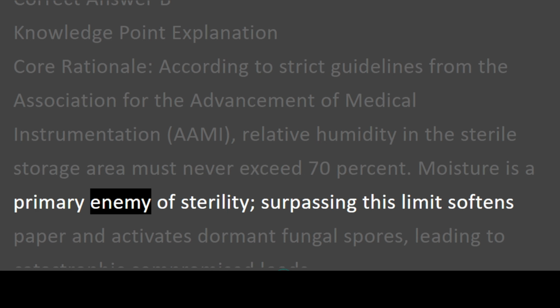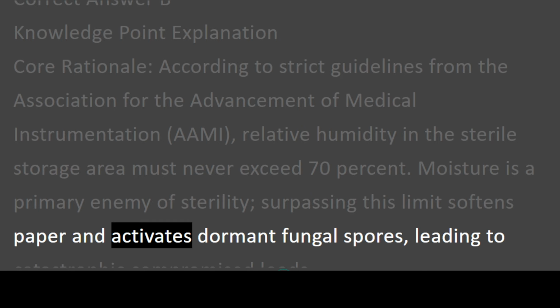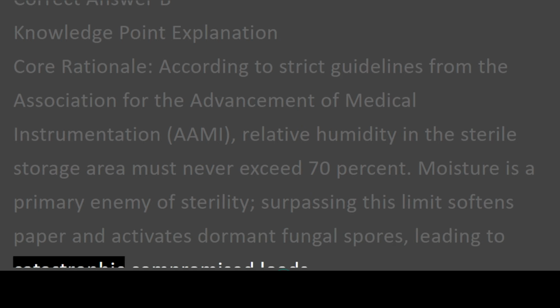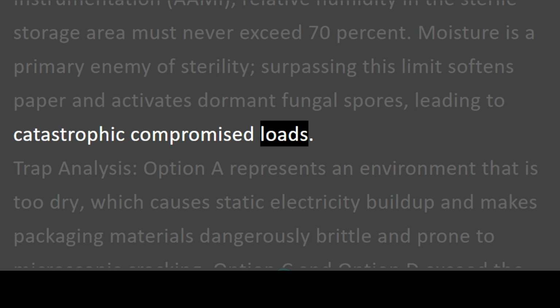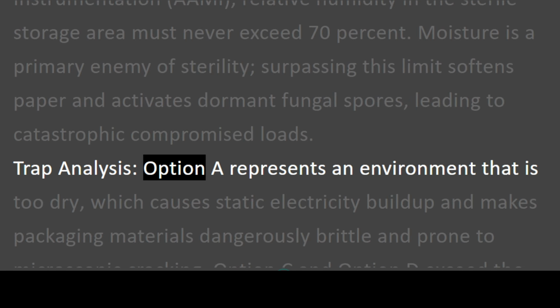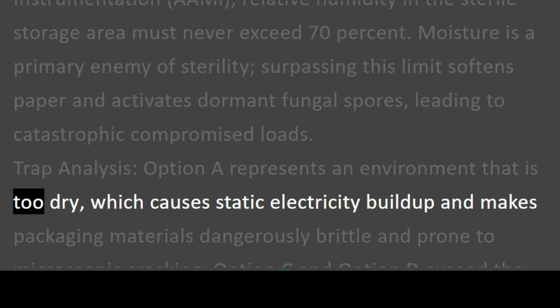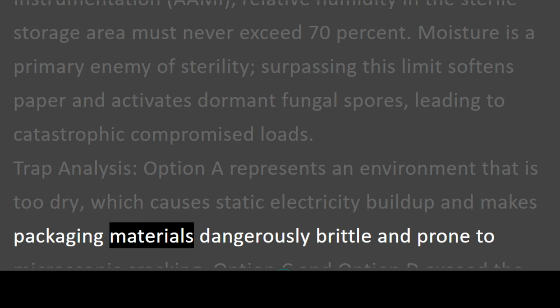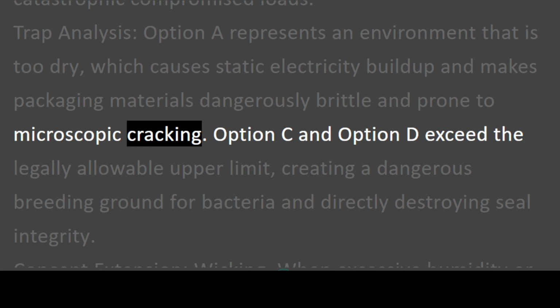Moisture is a primary enemy of sterility. Surpassing this limit softens paper and activates dormant fungal spores, leading to catastrophic compromised loads. Trap analysis. Option A represents an environment that is too dry, which causes static electricity buildup and makes packaging materials dangerously brittle and prone to microscopic cracking.